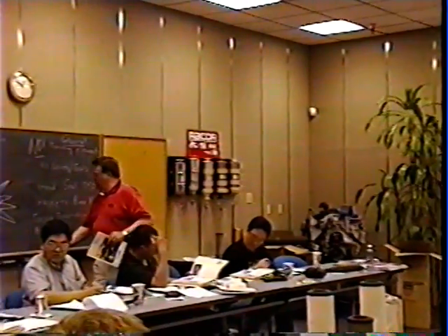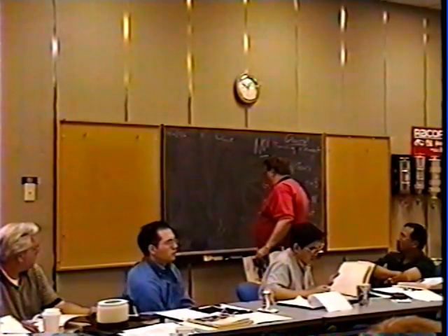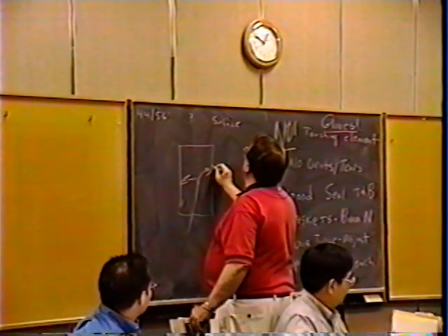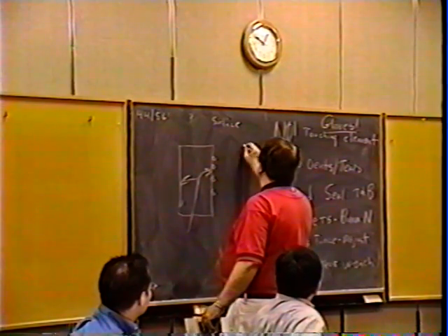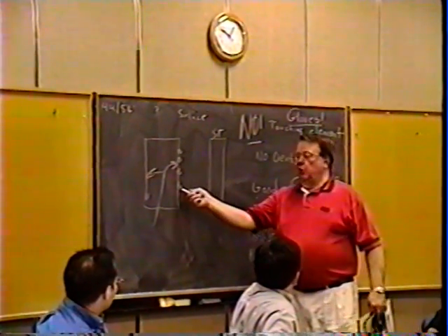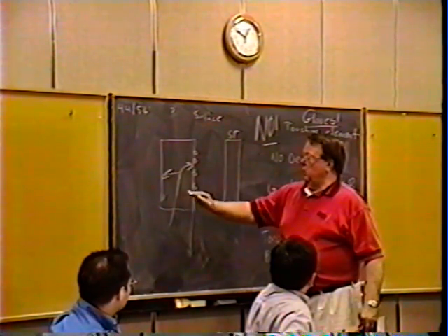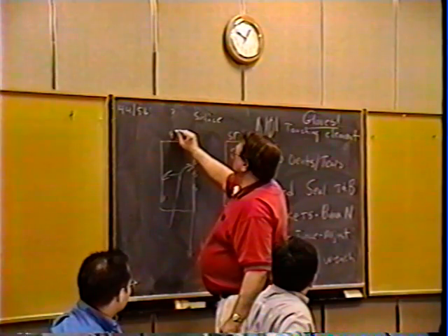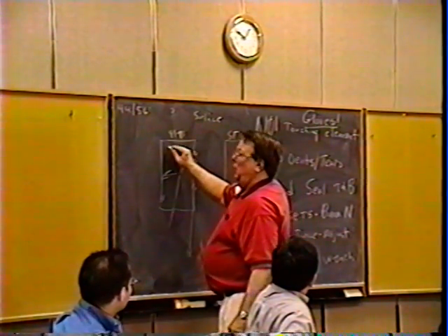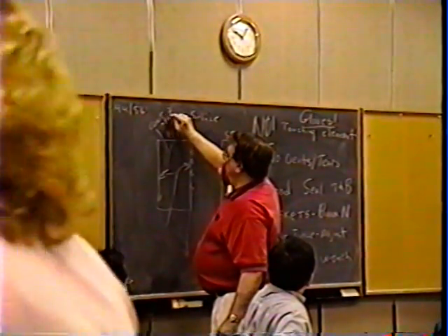Why is it important that we have large water droplets? The larger the droplet, the faster it will fall down. That's one point. Now, here's our coalescer. We're flowing out, and we have nice big water droplets. Over here, we have a small Teflon separator. We're going to use just plain old physics. These are heavy, so they're going to drop to the bottom. Its basic job is to get 98, 99% of the water out immediately and get it to the sump. Its other job is to get the contaminants out down to 0.3 micron.